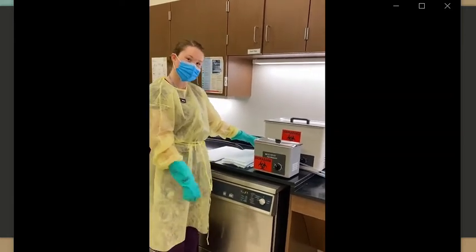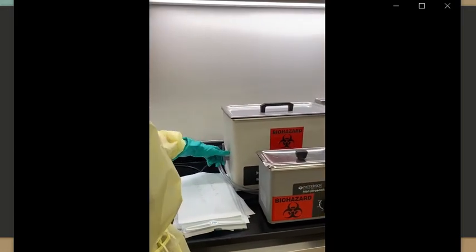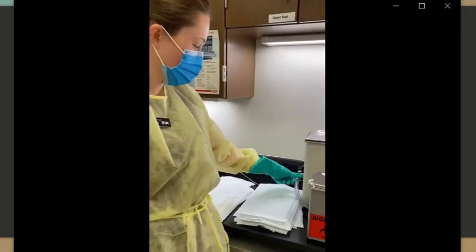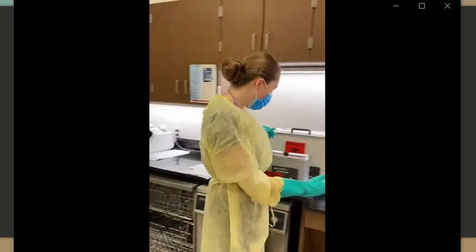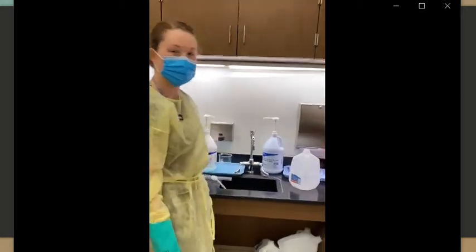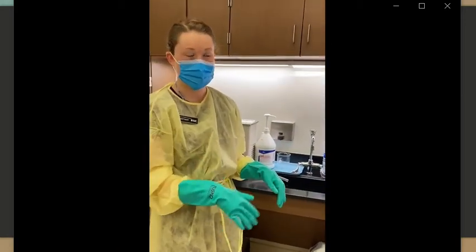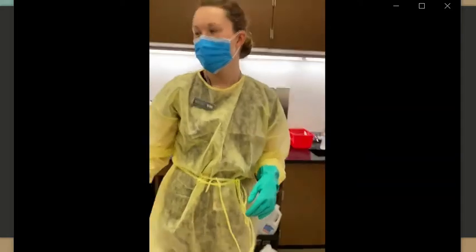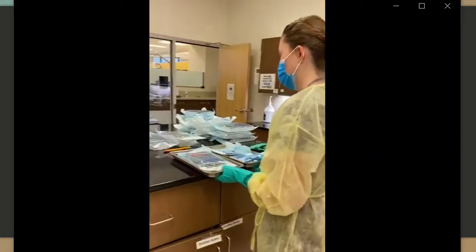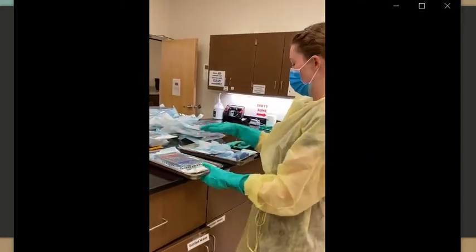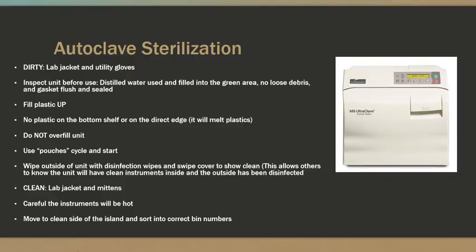Over on the side, you can see this is where you would flip it up and allow water to drain out, and you just shut it back to ensure that it's going to hold water and not drain off into the sink. If you don't check that it is completely sealed, it could run out into the sink and burn up the ultrasonic if it is running.